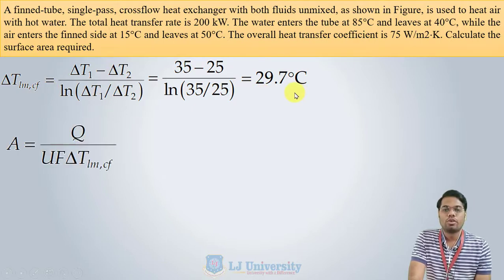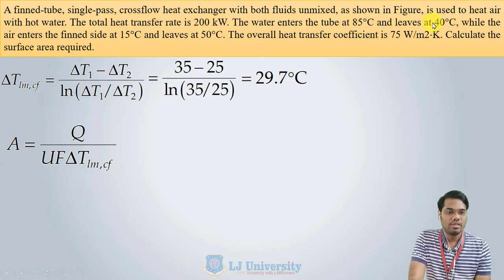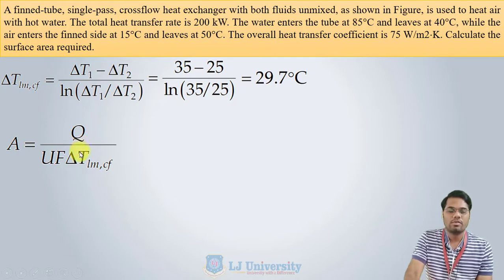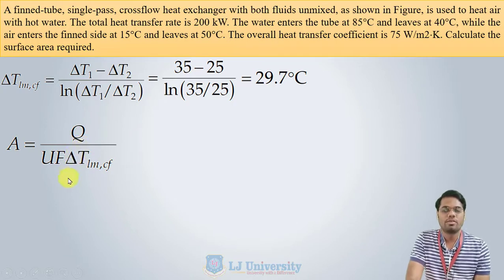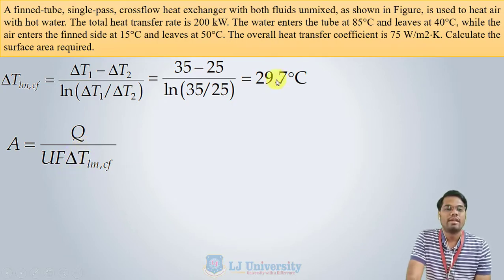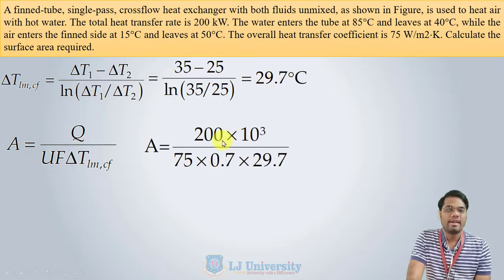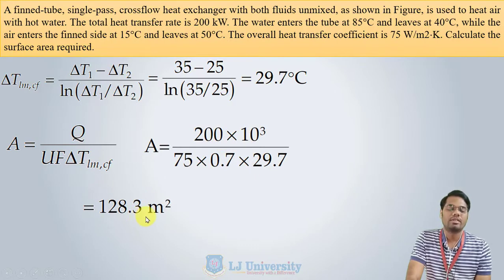Putting all values into Q = U·A·ΔT·F — with Q = 200 kW, U = 75 W/m²K, F = 0.7, and ΔT = 29.7°C — we get the required surface area as 128.3 m².